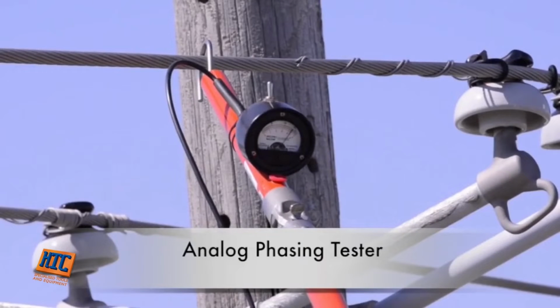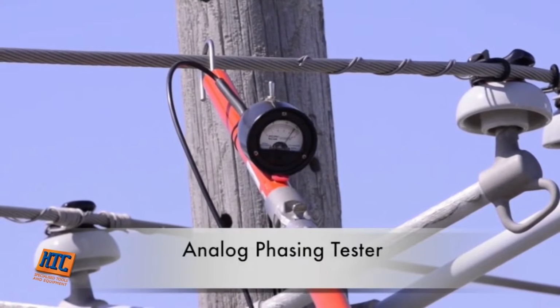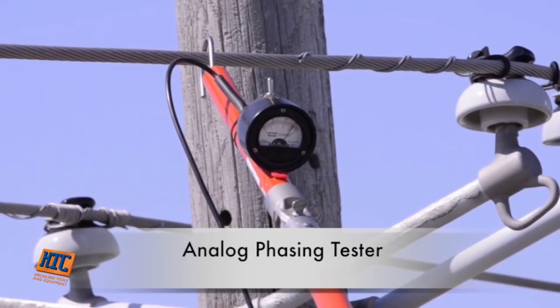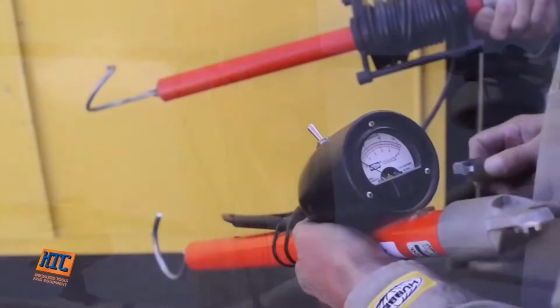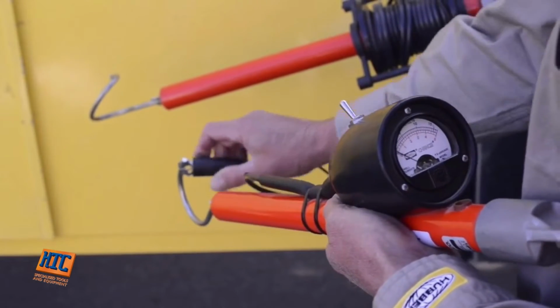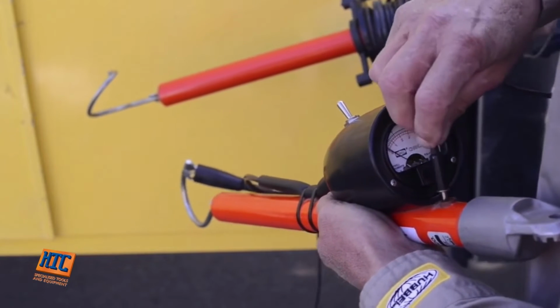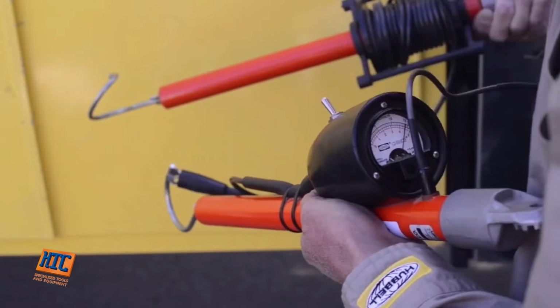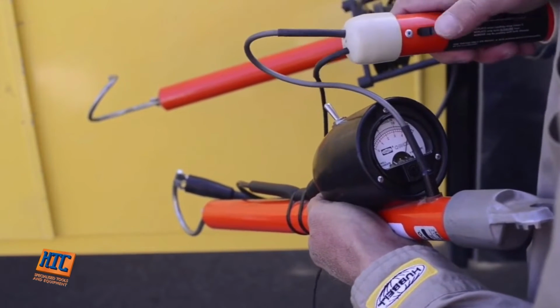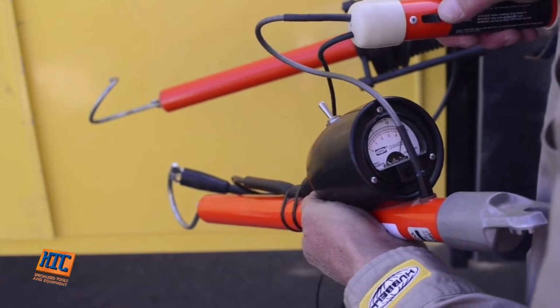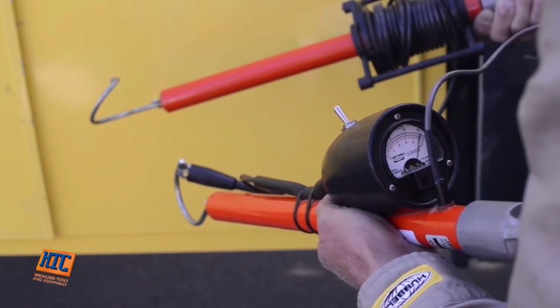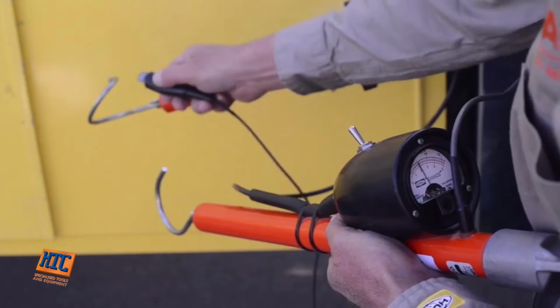Now, turning to the Chance analog phasing tester, first in a typical overhead application. Start by pre-checking the meter for operable condition using the phasing meter tester specified in the instruction manual. First, connect the alligator clip onto the hooks, then insert the probe into the meter jack. This pre-check must be performed before each use.